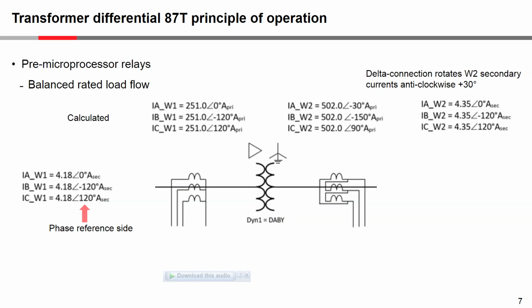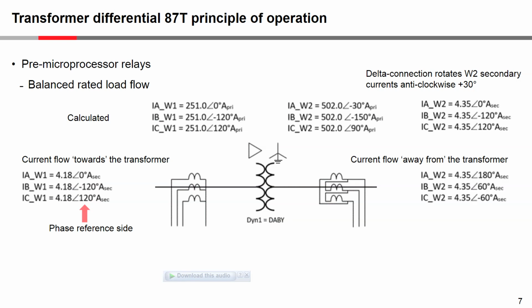Whereas if you look at the currents after the delta connection, okay, on the Y side, that delta connection is, as I said, shifting or phase rotating that 30 degrees, and so these currents that would flow out of the CT delta connection on the winding 2 side would now be aligned. Okay. Then the one thing to remember, and this has really got to do with the reference direction that the relays work on, is that on the high side, balanced load flow would be current flow towards the transformer, whereas on the winding 2 side, it would be current flow away from the transformer. So actually, for the way the relay would see this, we would need to see those currents, because they're flowing away from the transformer, as being shifted by 180 degrees.